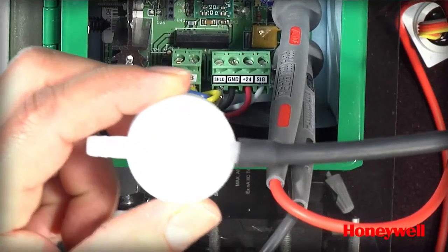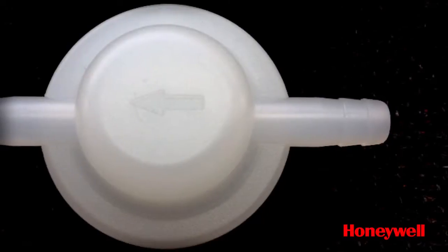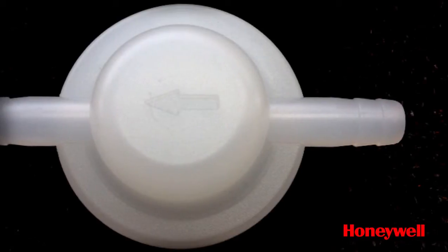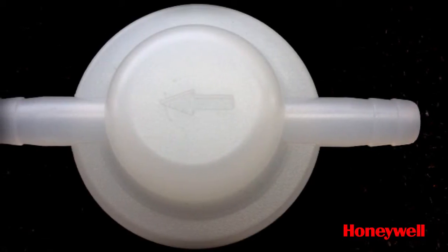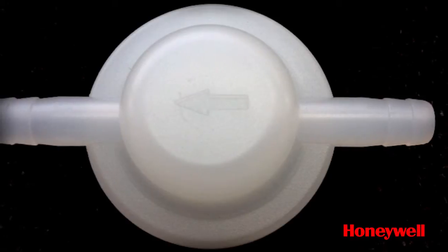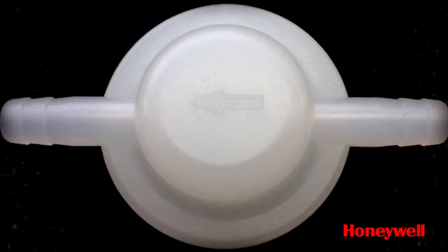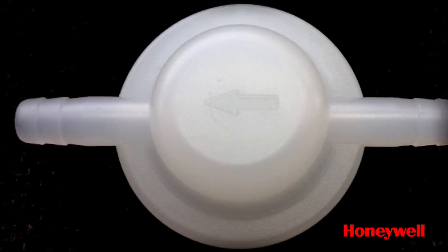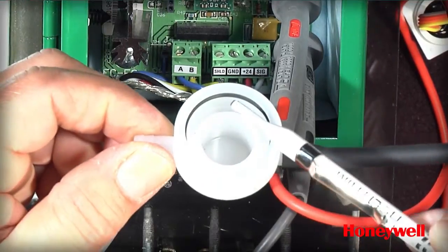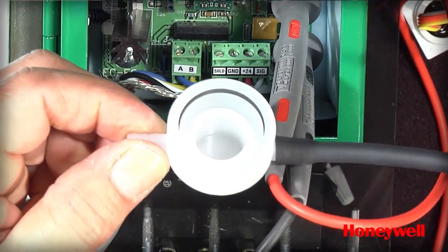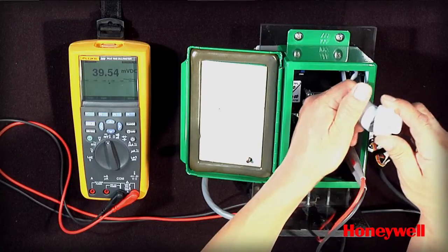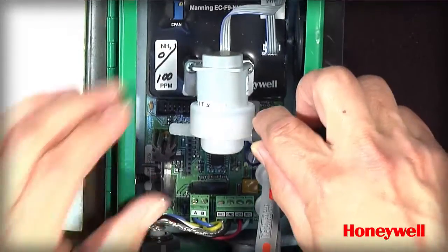After the sensor has been attached, connect the calibration adapter. Make sure to connect the gas in the direction of the arrow located on the top of the adapter. Flow rate is critical. To ensure best performance, please use a 0.3 liter per minute flow rate. The adapter has an O-ring to ensure the airtight connection. Connect the regulator to the top of the adapter and turn on the gas.